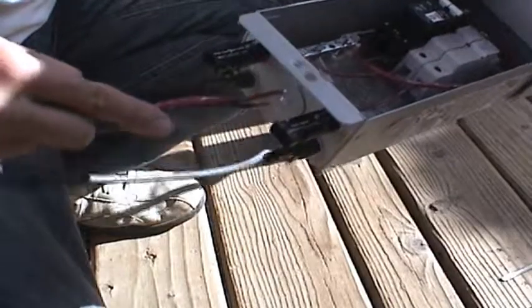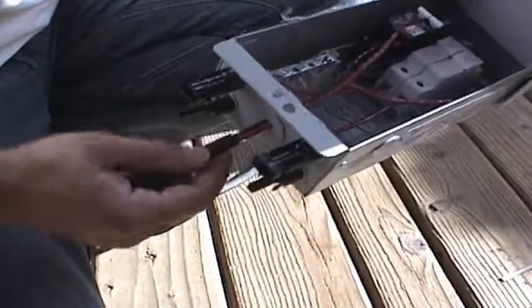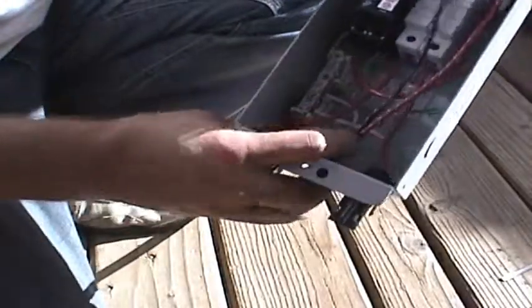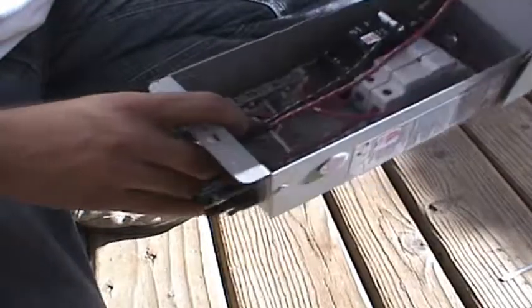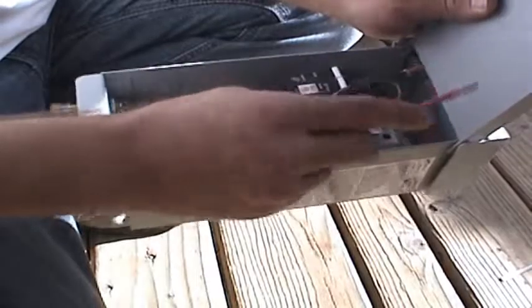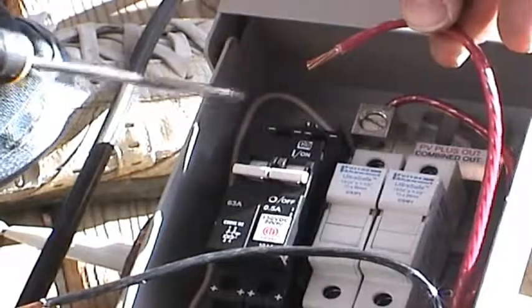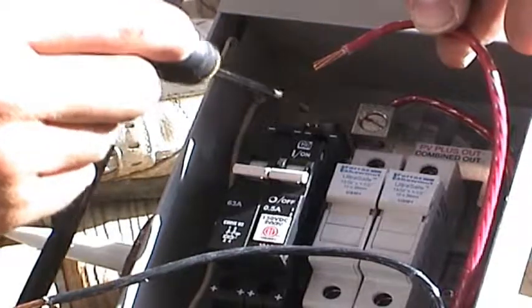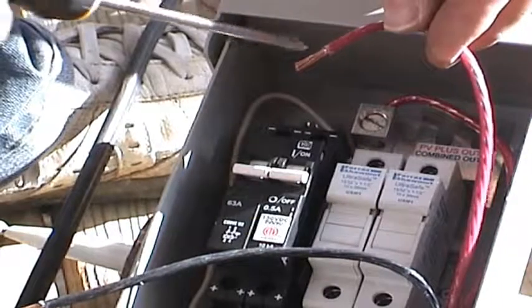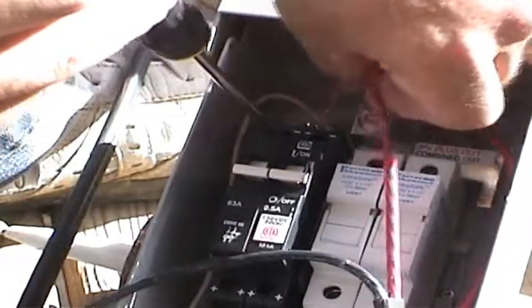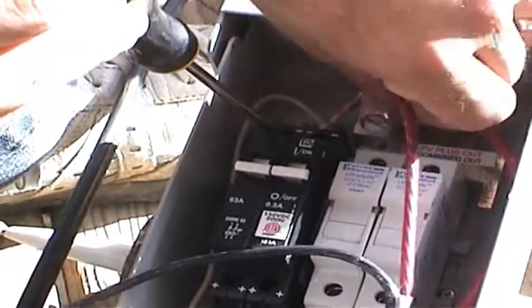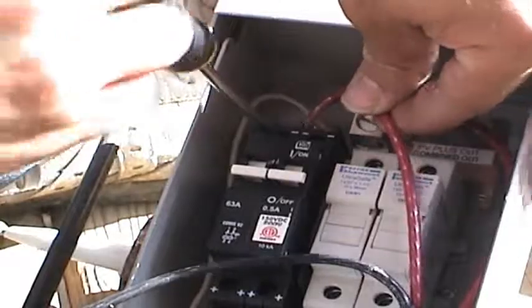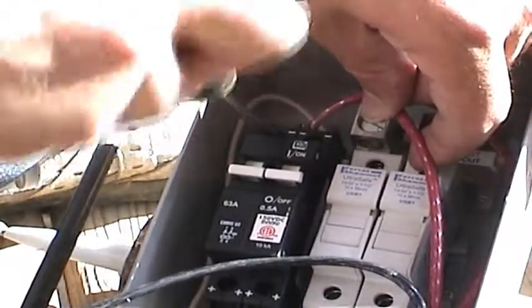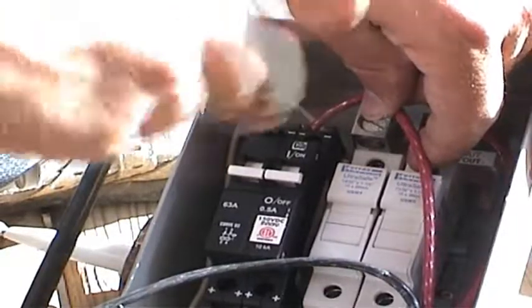Now let's feed the outdoor cable into the combiner box. Pull it through until some of the outside black skin pokes through into the combiner box. And then let's go ahead and install the red wire. The red wire is going to connect to the top of the GFP device. Notice again that the white wire is connected to one side of the GFP device. So we're going to connect the red wire to the other side of the GFP device. Let's go ahead and loosen the screw. Slide that red wire down into the GFP device. Make sure there's no bare wire showing, and tighten down the screw.